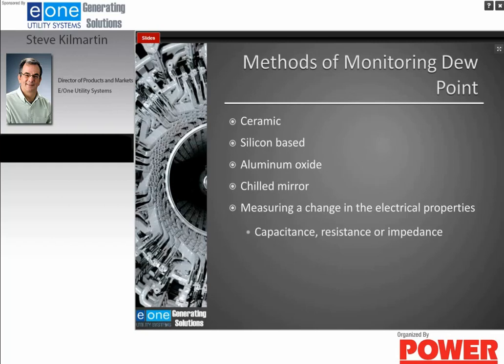Methods of monitoring dew point, there's several methods. You can use a ceramic sensor, a silicon-based sensor, aluminum oxide sensor. Chilled mirrors, I'm not aware of chilled mirrors ever being used in a generator, although chilled mirrors are the standard outside of a generator. All of the top three sensors, the ceramic, silicon, aluminum, they're measuring a change in the electrical properties, whether it be capacitance, resistance, or impedance, and that's how they're determining the dew point.